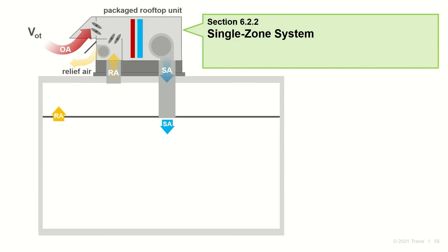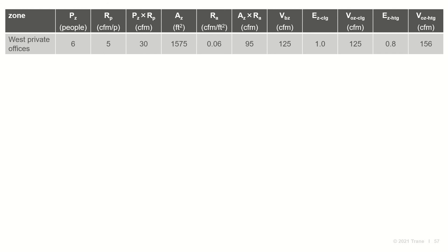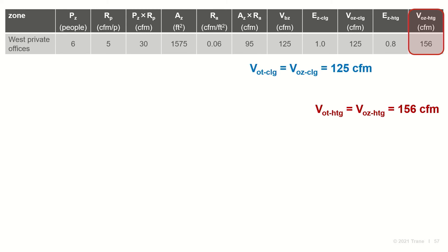Starting with the single zone system, since all outdoor air entering a single intake is delivered to one zone, this calculation is simple. According to Standard 62, the required system intake flow V-sub-OT equals the corresponding zone outdoor air flow V-sub-OZ. For our example, a separate package rooftop unit serves the west private offices zone, so V-sub-OT equals 125 CFM in cooling mode. Because E-sub-Z is less than one in heating mode, the intake flow is higher at 156 CFM.